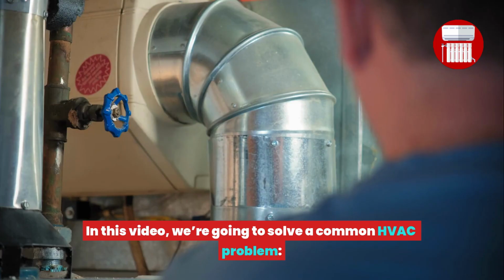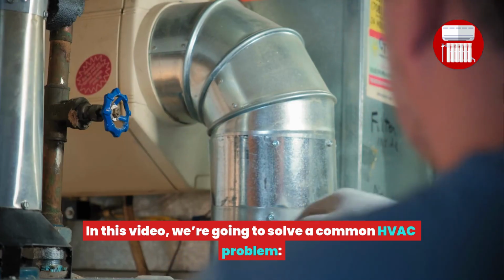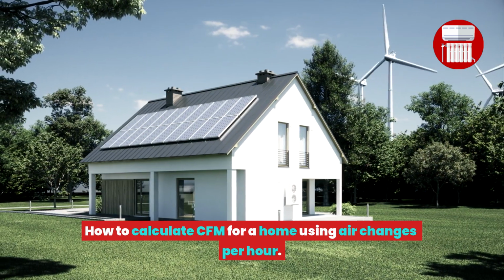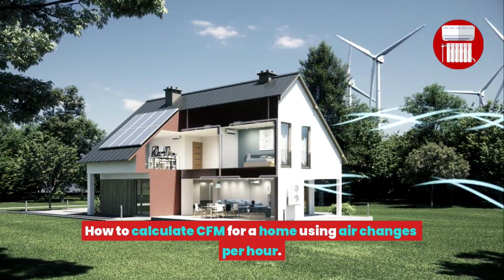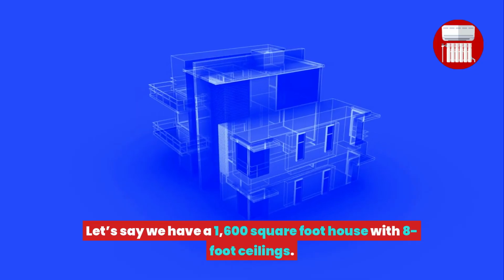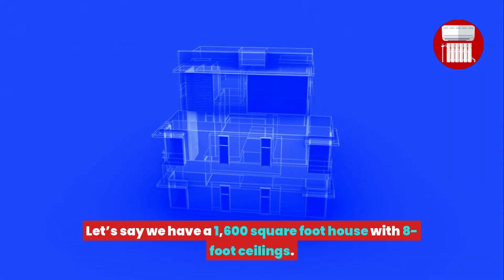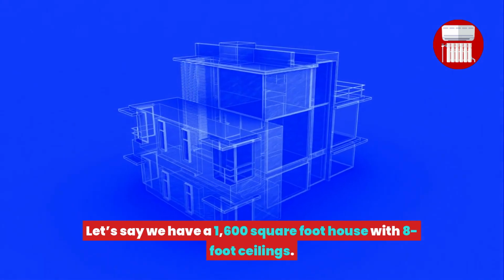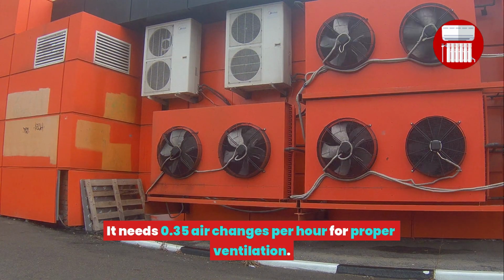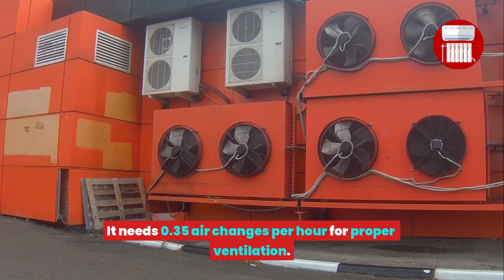In this video, we're going to solve a common HVAC problem. How to calculate CFM for a home using air changes per hour. The example. Let's say we have a 1,600 square foot house with 8-foot ceilings. It needs 0.35 air changes per hour for proper ventilation.